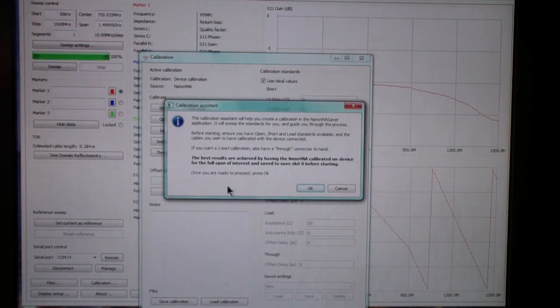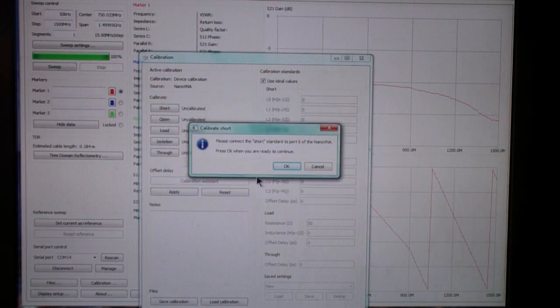For example, it says here how to do it if you just want a 1-port calibration, or what to do if you want a 2-port calibration. So it says once you're ready to proceed, press OK. So you click OK, and then it says connect the short standard to port 0. Now what I'm going to do is go through the calibration, but I'm not going to do it on video because you've seen that in one of my previous videos, and there must be 50 videos online that show you how to do that. So I'm going to pause the video right now while I go through the calibration from 50 kilohertz to 1500 megahertz.